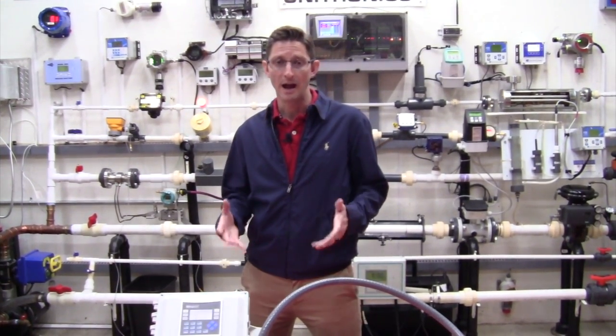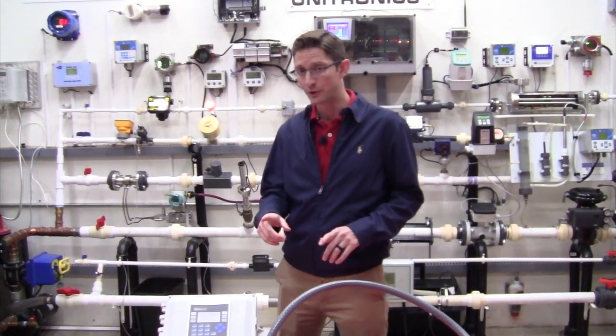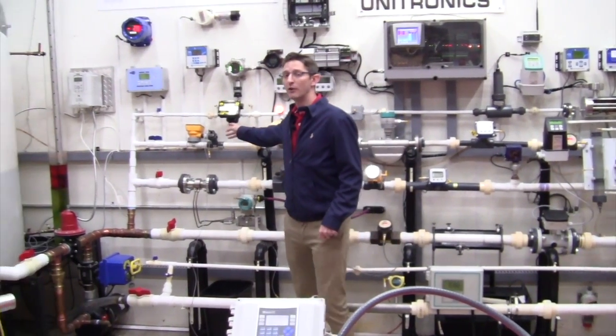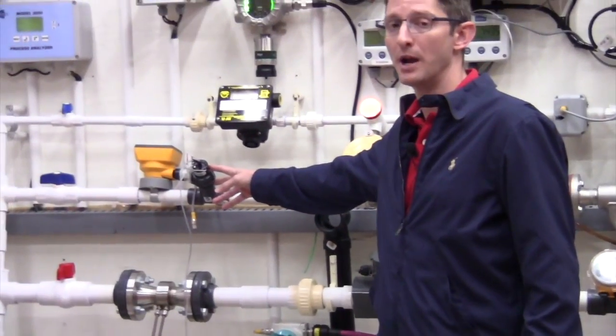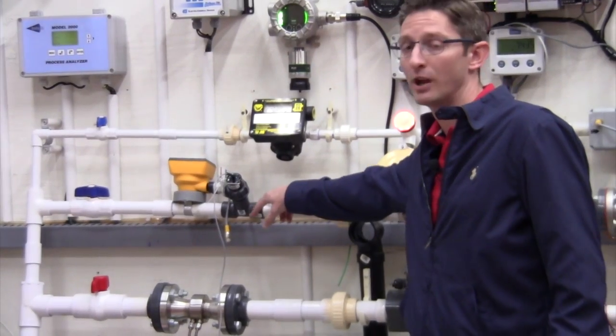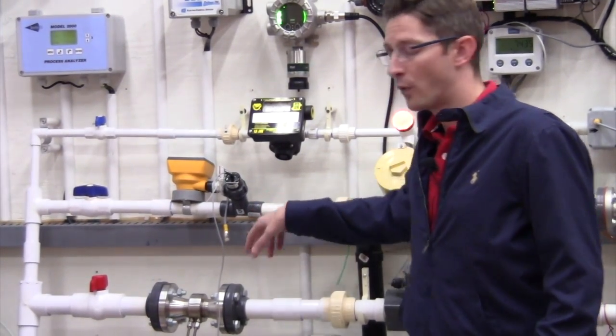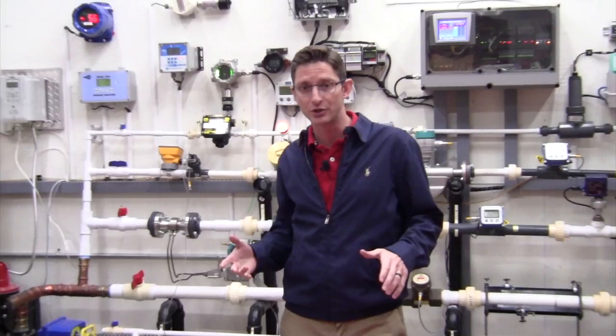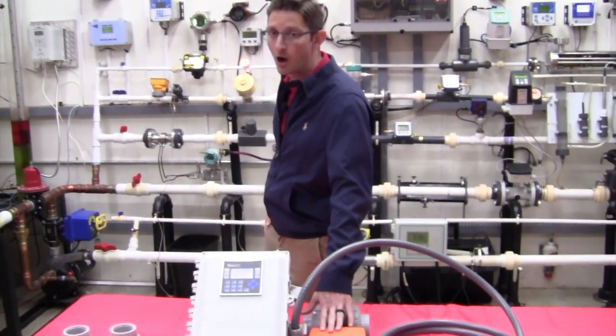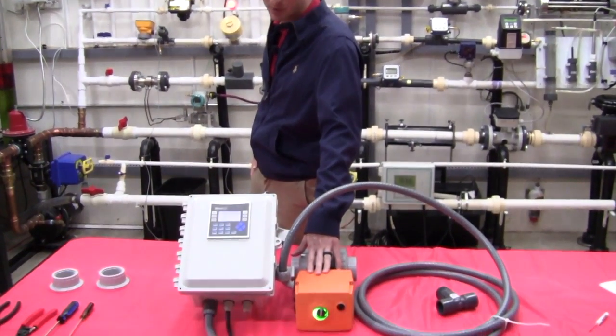So now I'm going to show you how to actually do a calibration. The first thing you'll notice is we now have our flow meter installed into the pipe in our 1-inch line in a 1-inch T-fitting. For the purposes of this demonstration, we do not have our valve installed into the pipe.